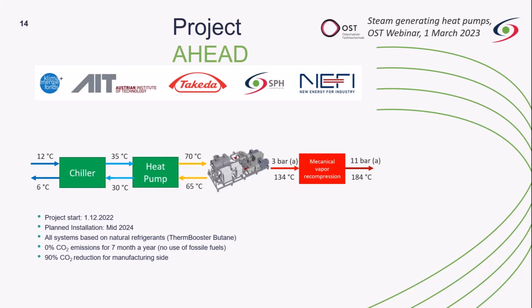So from a chiller, the water is taken to go into a, let's say, low temperature heat pump. It's also an ammonia heat pump in this case. Then we will do the phase change with our heat pump. So we will deliver 3 bar absolute into a mechanical vapor recompression unit, which then delivers 11 bar of steam. Yeah, so this project is also published, and you can read about it at AIT or NEFI in Austria. So yeah, that's my presentation.